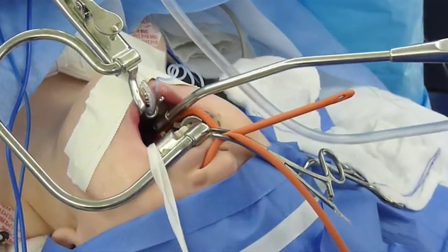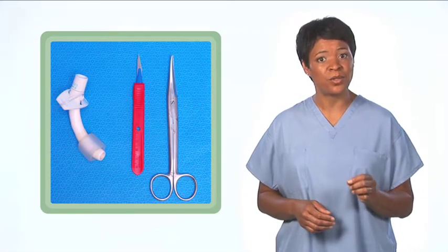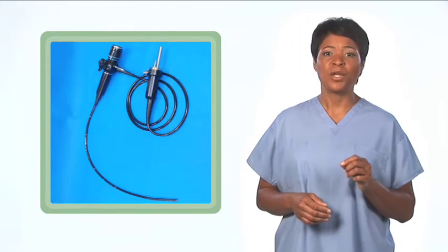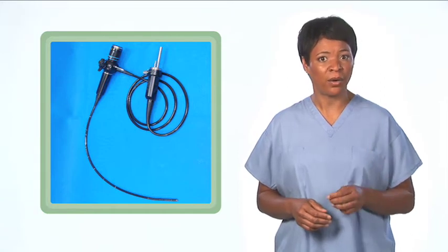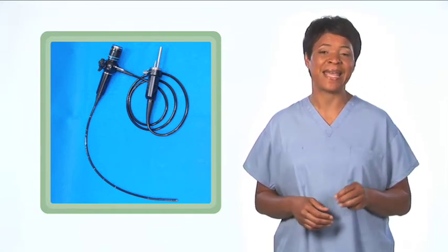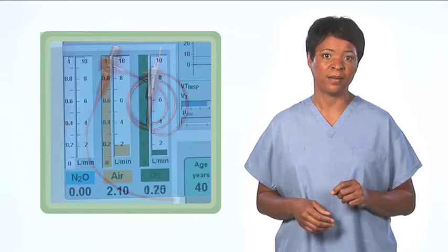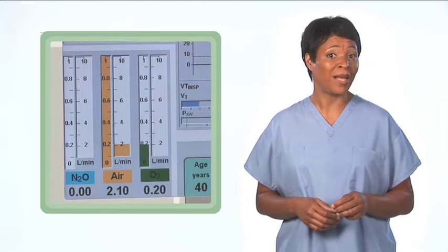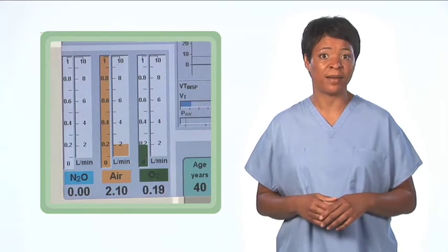If an oxygen concentration greater than 30% or nitrous oxide is used, suction deep within the oral pharynx with a metal cannula prior to using electrosurgery. During tracheostomy, patients often require increased oxygen concentrations to avoid hypoxia. Fires may occur when the oxygen-enriched trachea is entered with an electrosurgical instrument. A scalpel or scissors should be used instead to enter the oxygen-enriched trachea. During surgical bronchoscopy, fire can occur when a laser fiber or electrosurgical device is activated in the oxygen-enriched lung. Oxygen concentration should be reduced to less than 30% when the surgical device is activated.